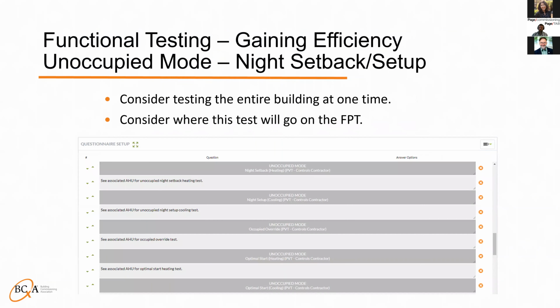Now we head to the dark side. For anything involving scheduling, I like to test it as few times as I can. So I usually get all the occupied mode testing done first, then test unoccupied at one time. If you think about it, why test the whole building in occupied, but only test part of the building at a time in unoccupied mode?